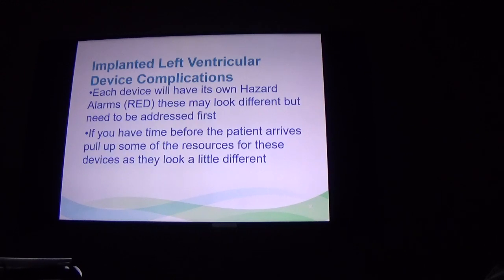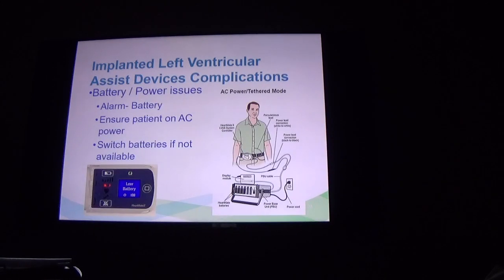Each device has its own red hazard alarms. Again, each is a little bit different because they're all different manufacturers. So when you're in your community hospital, knowing when these devices are placed and what specific device you're going to have to deal with can be extremely helpful, and printing them up is extremely useful, because then you can quickly flip and know exactly what alarm is going on and try to address it. Again, if it's your first time dealing with the patient, you may not have that luxury.